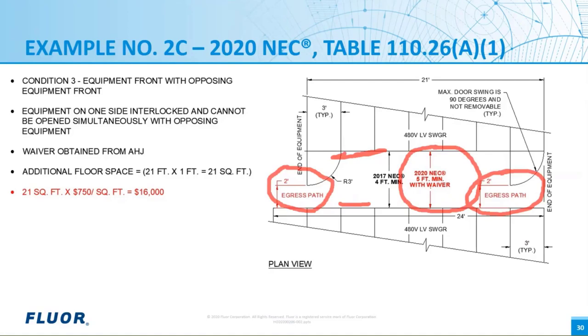Where this is allowed, the installation must be shown to be as safe as or safer than what the NEC allows. Now, we know most AHJs prefer not to write a waiver as a standard practice, but if somebody was confronted with an existing installation where equipment is being replaced, something like this might be the only reasonable option while still maintaining equivalent safety for the worker. The basis for the special permission in this example is the opposing equipment will have some sort of interlocks or some procedures in place that prohibit the opening of the equipment doors on both sides at the same time. That way, there's still a 24-inch egress path available.